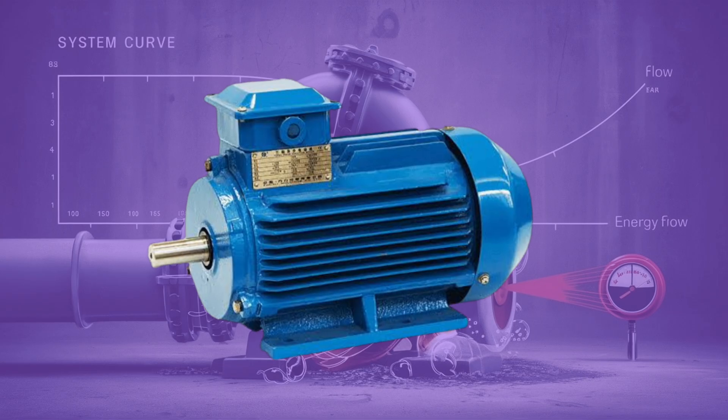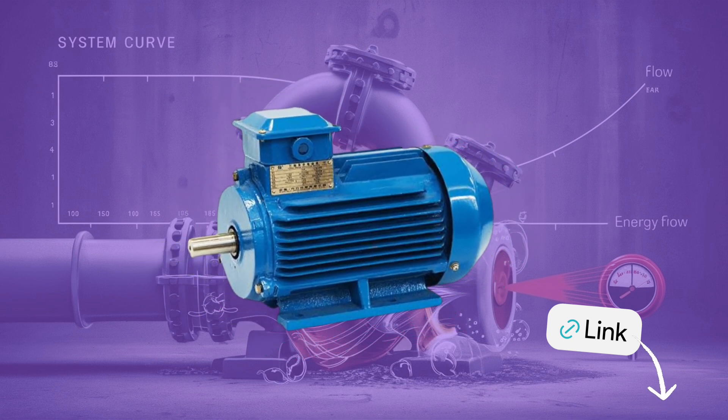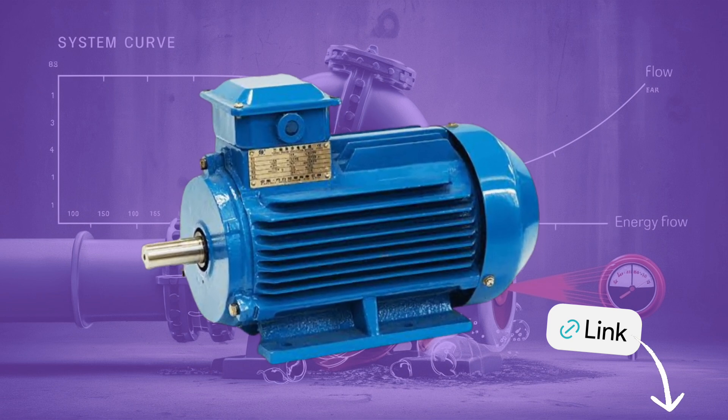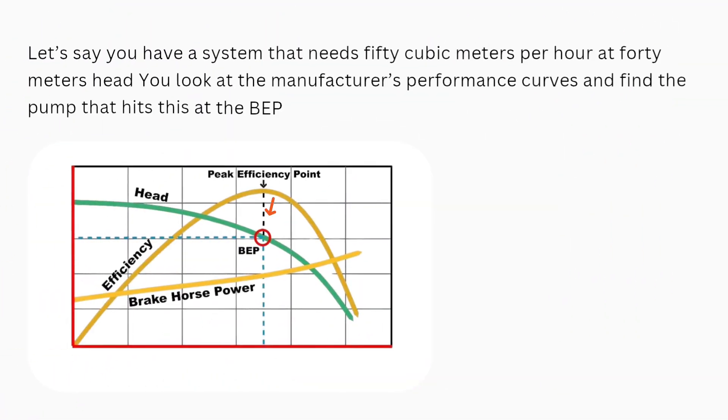If you want to deep dive into centrifugal pump videos, you must check out our centrifugal pump playlist. Real life example. Let's say you have a system that needs 50 cubic meters per hour at 40 meters head. You look at the manufacturer's performance curves and find the pump that hits this at the BEP. That's your best choice. Efficient, stable, and reliable.